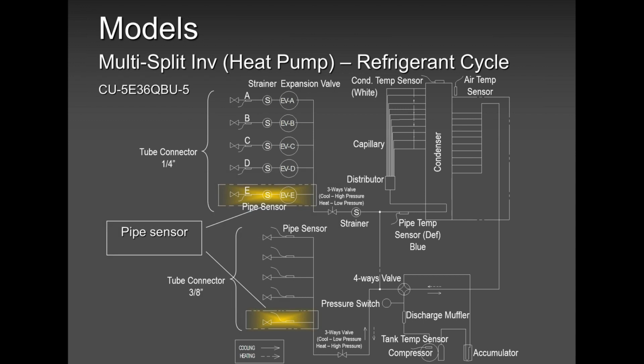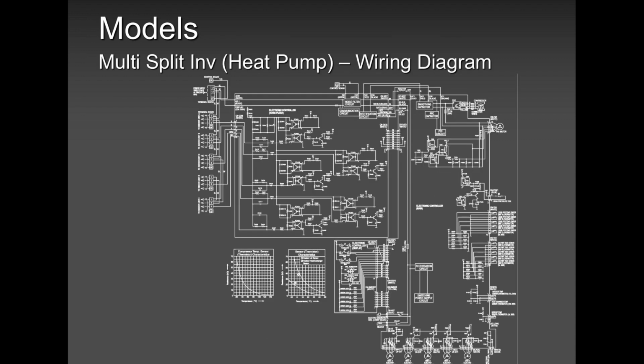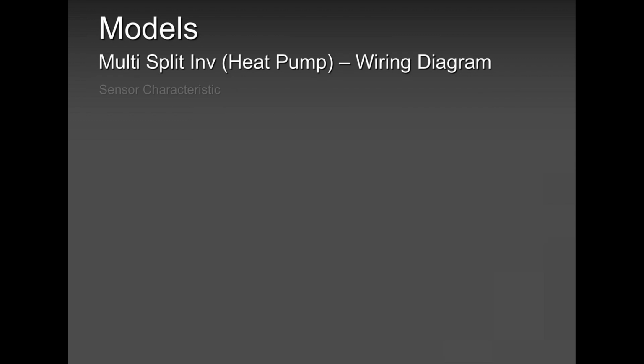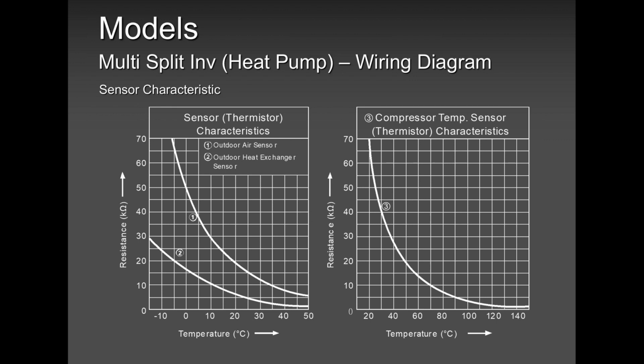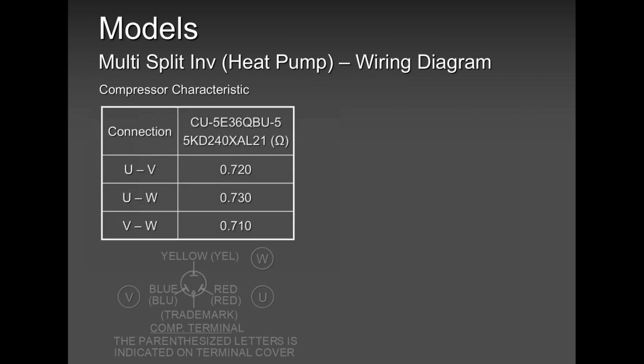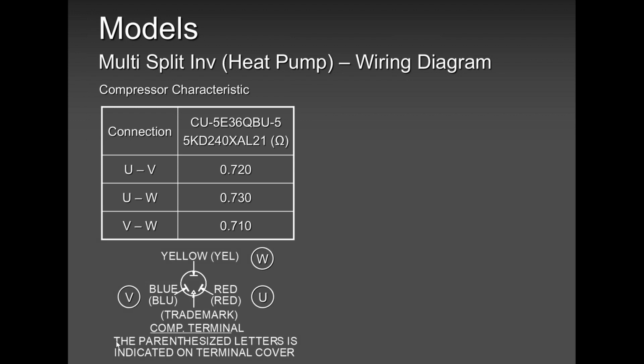Sensors are everywhere. We have liquid and gas sensors, suction and liquid sensors, compressor discharge. Okay, compressor discharge to stop the compressor from running too hot. We have the ambient sensor for regulating the pressure and regulating the fan speed. This is a wiring diagram that you will see on the outdoor unit top panel. There is a sticker there. You can follow it in the service manual or in your app. On the app or a service manual, you'll find this chart. Check the sensors. I mentioned to you earlier, very rarely they go bad. But I'll tell you, they do go bad sometimes. And in most cases, I've noticed the sensors go bad after 8, 9, 10 years.